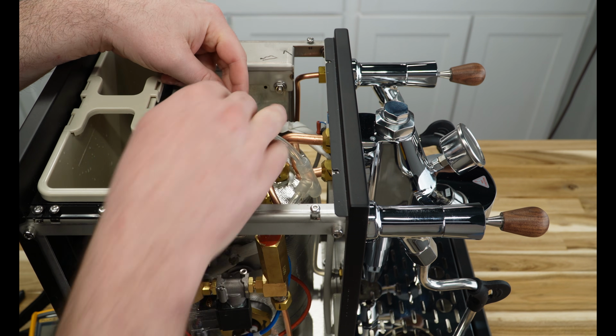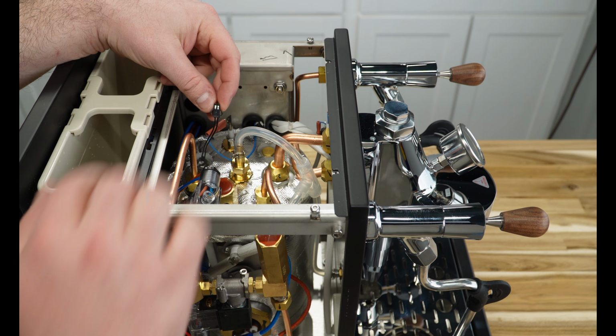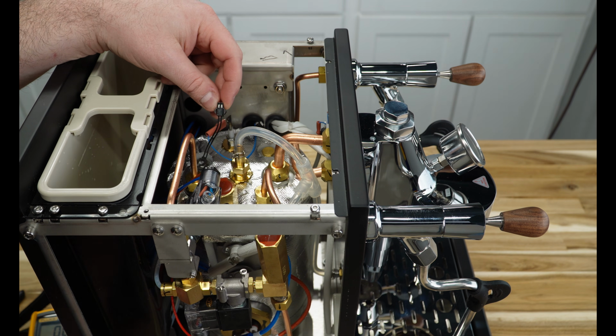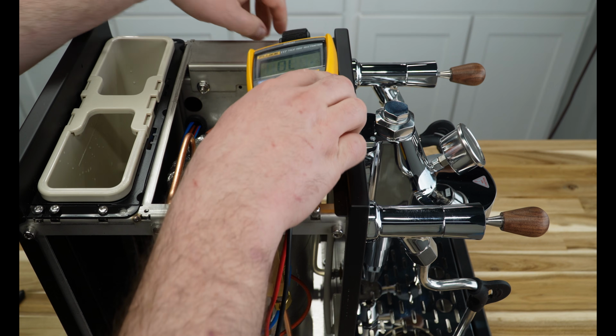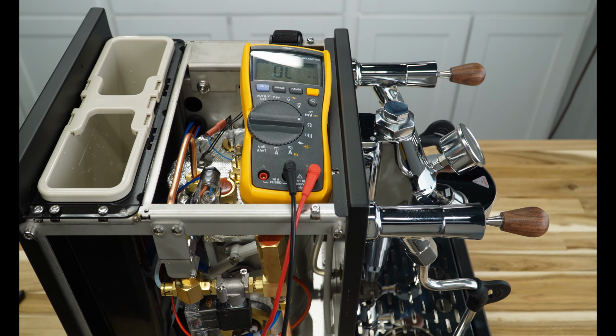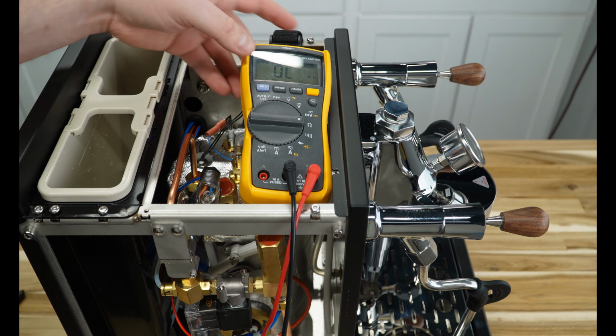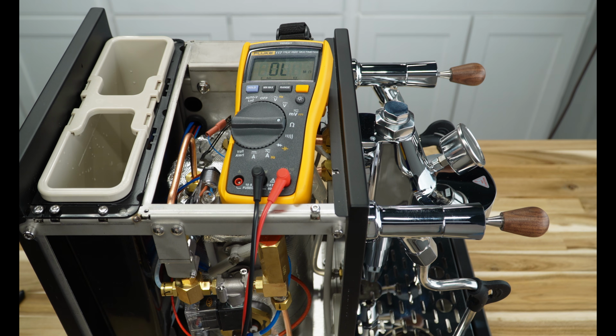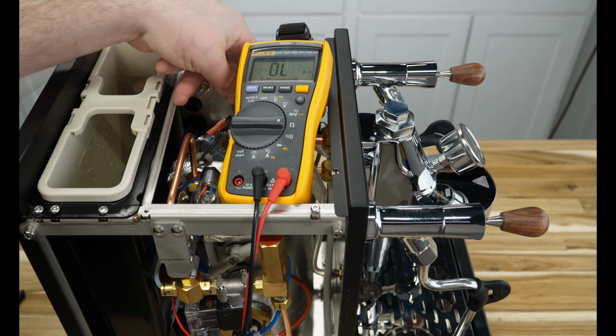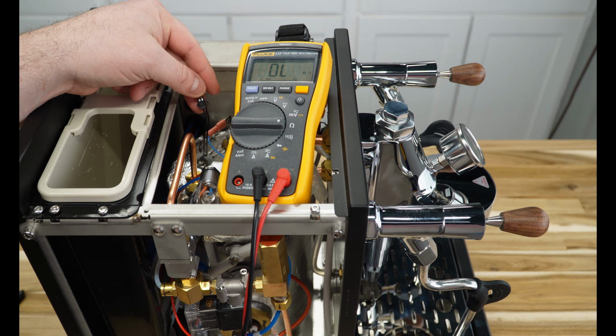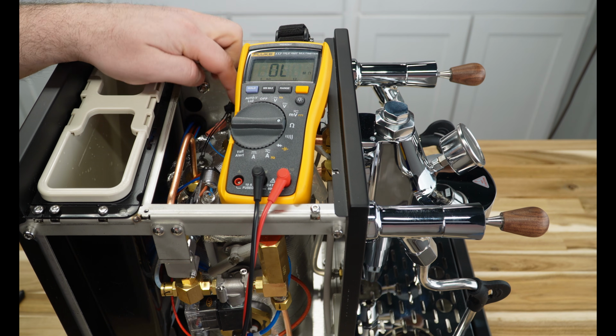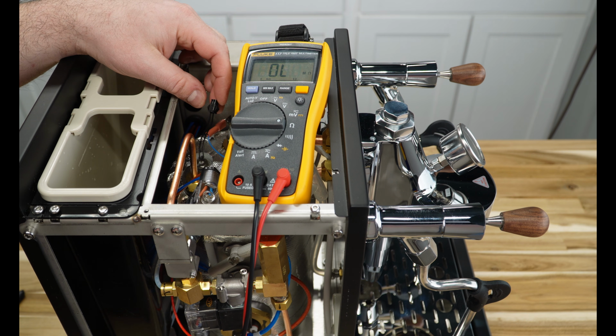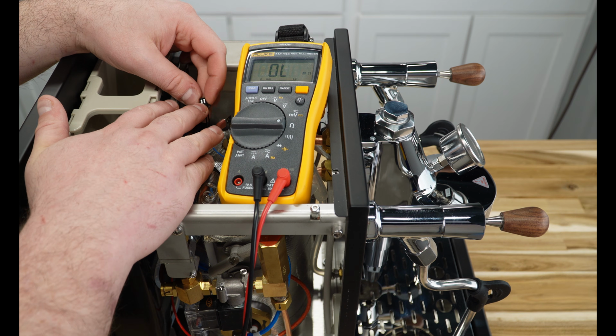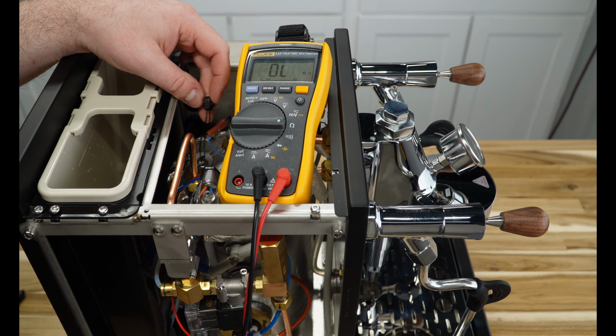It can be a little bit difficult. Not all of them are the same, but you can see two contact points at the top, and that's what we're going to do a quick test on. If this probe were bad, it's either going to say OL because there is no continuity through that probe, or it could also be a really high reading, meaning that one of these is going to the base of it. They are grounded, we don't need to go into all this stuff, but if it's very low or very high, there's a big potential that this is damaged.